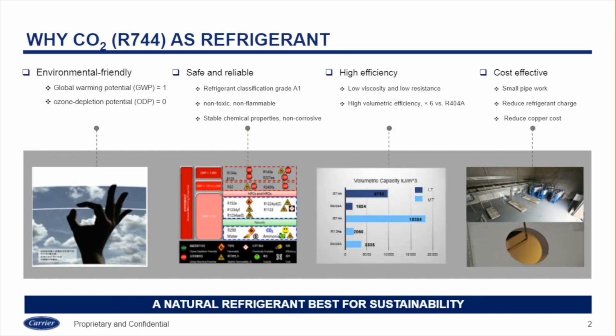This one shows why CO2 is being selected as a refrigerant. Basically, we have four good reasons for CO2 as a refrigerant. The first one is that it's an environment-friendly refrigerant: the GWP equals 1 and the ODP equals 0, which means it has no impact on the environment. The second and most important one is the safety of the refrigerant. CO2 is classified as A1, which is a non-toxic and non-flammable refrigerant. So it's pretty safe for residential and commercial application.